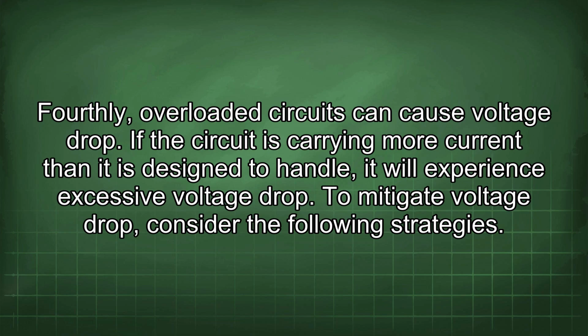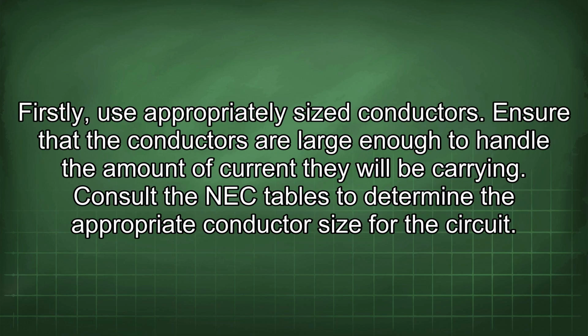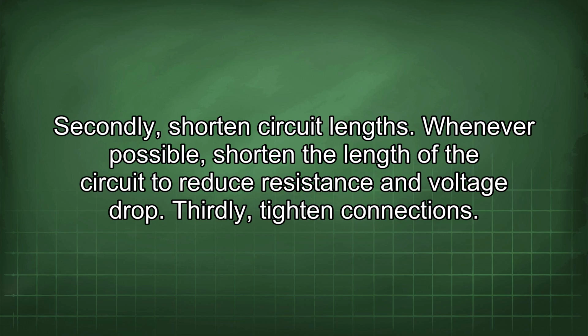To mitigate voltage drop, consider the following strategies. Firstly, use appropriately sized conductors. Ensure that the conductors are large enough to handle the amount of current they will be carrying. Consult the NEC tables to determine the appropriate conductor size for the circuit. Secondly, shorten circuit lengths. Whenever possible, shorten the length of the circuit to reduce resistance and voltage drop.